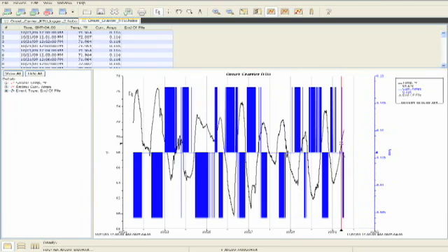We do see in a couple points our temperature inside the supply duct got up to 76 degrees. Our sensor was about 10 feet down from the unit itself. We'll be more concerned with the space temperature, our return air temperature, which is on our second logger, which I'll show you in a minute. So we can see along our graph here, the summary of it. We can see the temperature dip down to 60 at this particular night, and a couple times reached 76 degrees. Again, this is in the supply air duct.